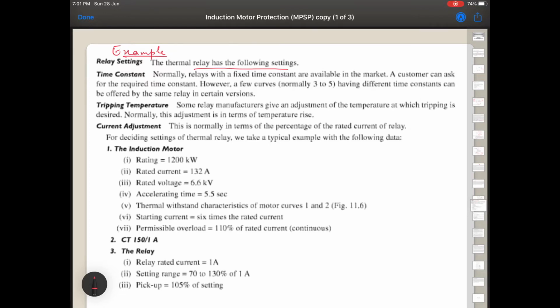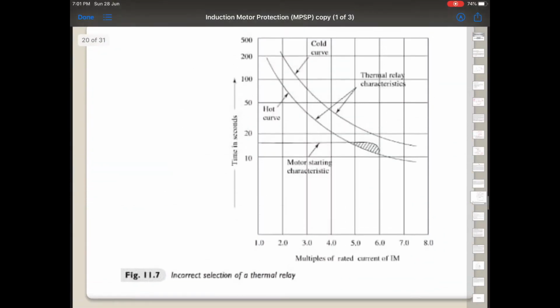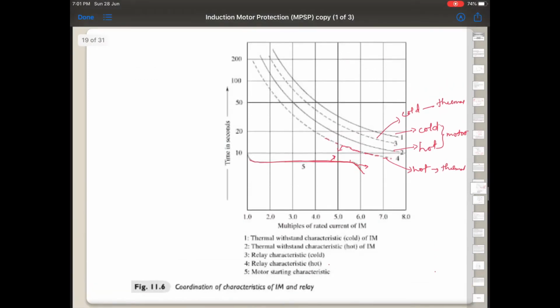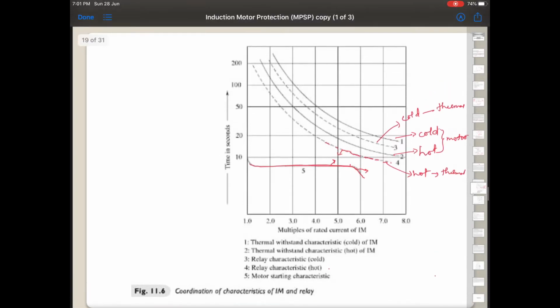The rating of the induction motor is 1200 kilowatt and its rated current is 132 ampere. It is of 6.6 kV, and the accelerating time, that is from no load to full load, is 5.5 seconds to reach the rated speed and rated current. Now the thermal withstanding characteristics of the motor, 1 and 2, have already been shown here. These are the hot and cold curves of the induction motor taken in this example.